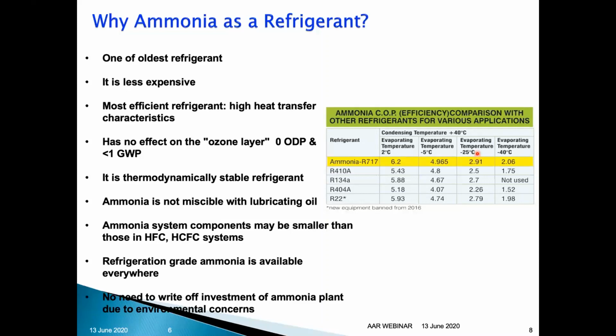So this is another thing: it is a single component, not a mixture of gases, so it is a thermodynamically more stable refrigerant. It is not miscible in oil, so you can very easily separate out the oil which is required for your compressors' cooling and operation, and it doesn't have an effect on your refrigerant system. And if you consider the capacity, we'll show you the slide on how the latent heat of ammonia is higher than other HCFC and CFC refrigerants. That's why you need smaller sizes of equipment and line sizes for a similar refrigeration capacity.